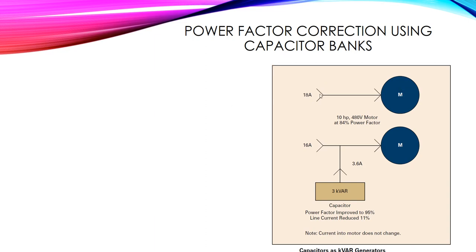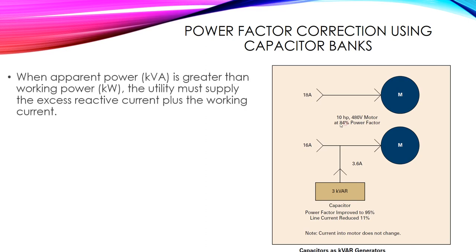Here is a simple example — we have a motor absorbing apparent power from the grid. The motor has values of 10 horsepower, 480 volts, and a power factor of 84 percent, absorbing 18 amperes from the grid. In order to reduce the current absorbed from the grid, we use a capacitor bank. In this example we added a 3 kilovar capacitor, which supplies a current of 3.6 amperes, reducing the grid current from 18 to 16 amperes.